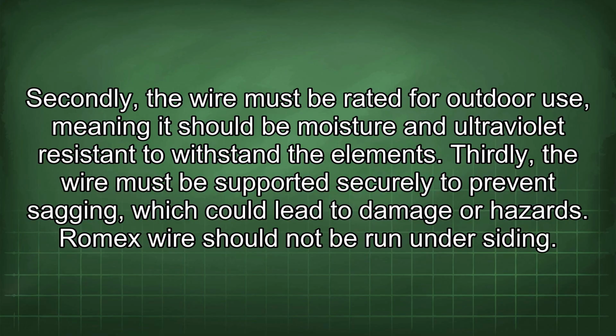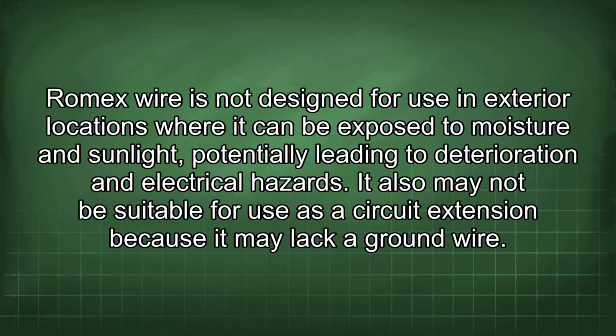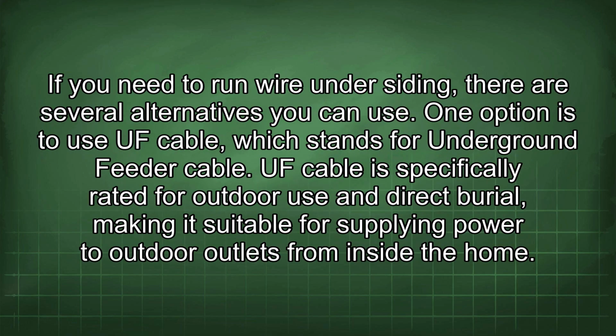Romex wire should not be run under siding. Romex wire is not designed for use in exterior locations where it can be exposed to moisture and sunlight, potentially leading to deterioration and electrical hazards. It also may not be suitable for use as a circuit extension because it may lack a ground wire. If you need to run wire under siding, there are several alternatives you can use.